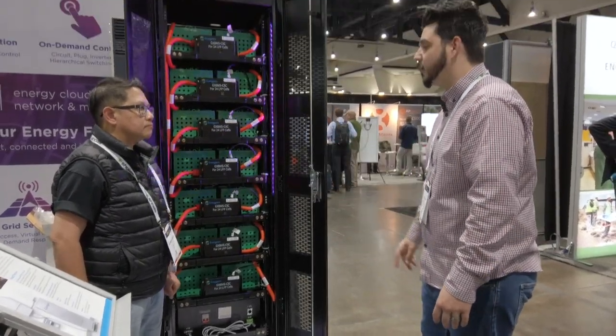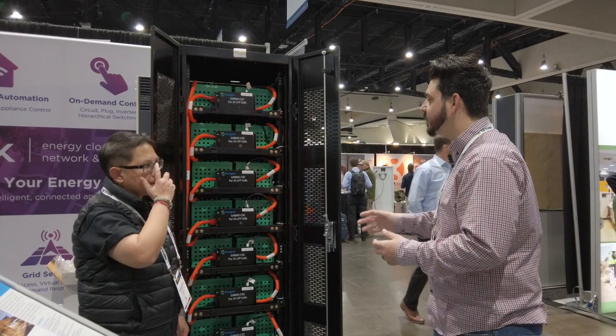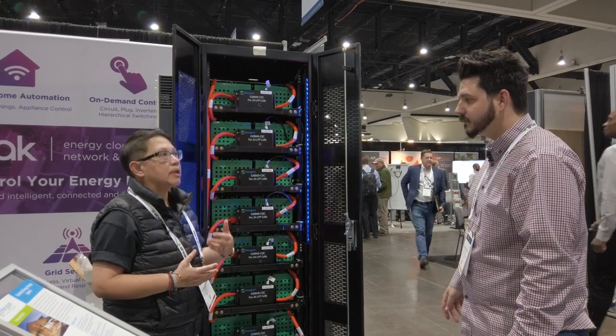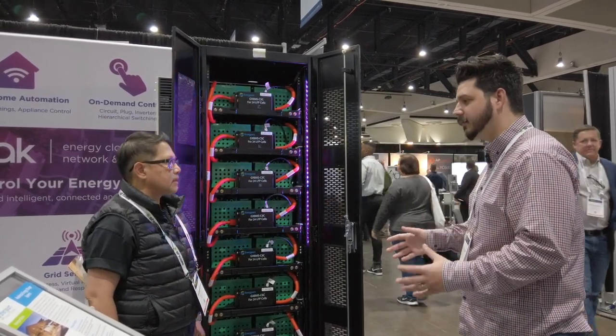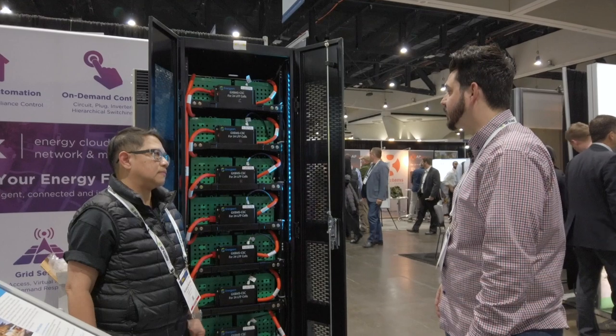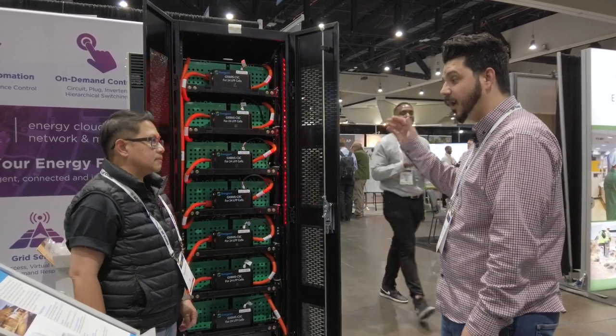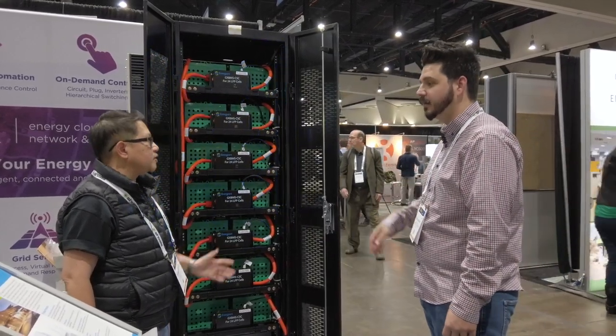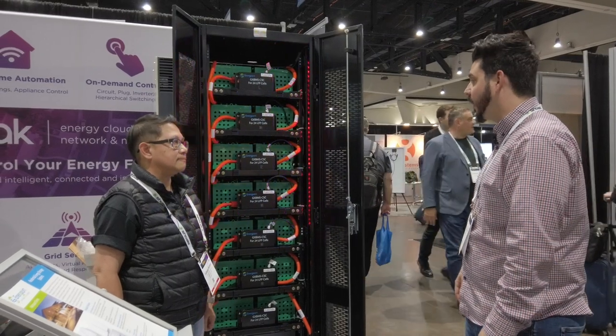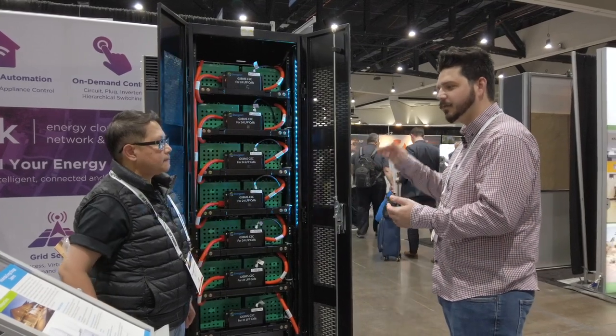What are we looking at for a warranty? We're looking at a 10-year warranty, which is industry standard. But since it's LFP, it should have a much greater life expectancy — and we're open to 10- or 15-year warranties as well. For cycle life, we're looking at about 3,500 to 3,600 cycles at 100% depth of discharge before it reaches 80–70% capacity. At 80% depth of discharge, you're looking at approximately 6,500 life cycles, and at 70% discharge, roughly 10,000 cycles.